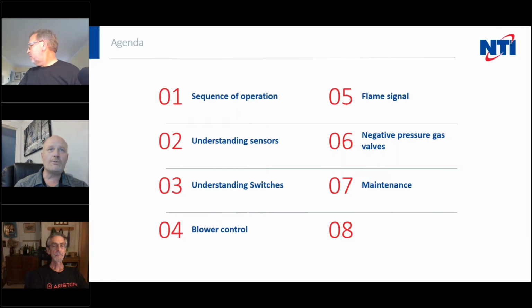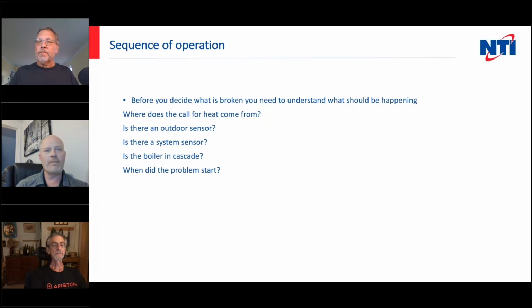Okay, so we'll start off with a quick sequence of operation. We're going to go through understanding different types of sensors, switches, how the blower is controlled, how flame signal works. We're actually not covering negative pressure regulated gas valves. I did that 2 or 3 episodes ago, so if you haven't seen that, you can go look it up. As for maintenance, I just didn't update the presentation title, so we're not doing that tonight either.